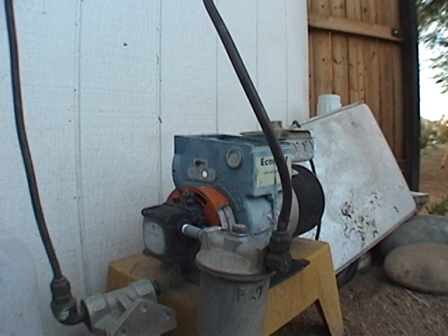This is the original filtration system that would normally be on the oil burner. The pump has been converted to a two-pipe system, meaning oil goes in and oil comes out. It's constantly circulating oil from the home's tank to the oil burner and back to the home's tank if it was in its normal position. So that's converted so the oil will go through it and go back out.